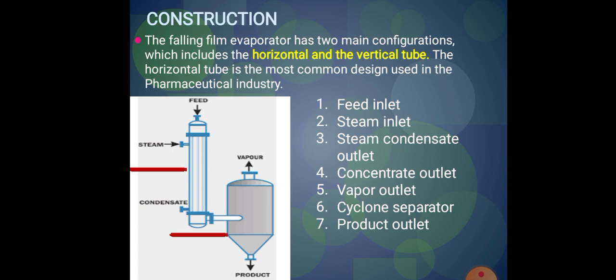There is a steam inlet where steam is introduced as the heating media, a vapor outlet in the cyclone separator, and a product outlet. The cyclone separator is an equipment used in pharmaceutical industries for the separation of gases and liquids — it separates the concentrated product from vapors. There is also a feed inlet at the top of the heat exchanger and a condensate outlet for removal of steam condensate.